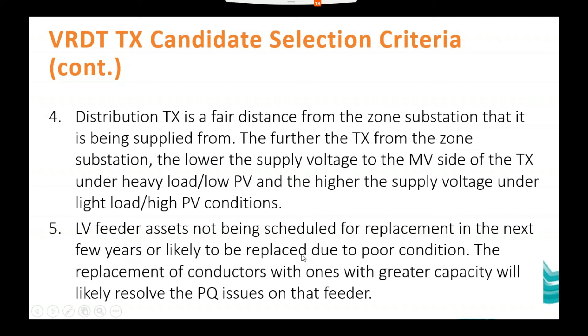And we also wanted to do it where the LV conductor assets were in relatively good condition. We didn't want the conductors to be in poor condition, because if those assets are in poor condition and you need to replace them, chances are you replace them with new conductor, which is a new standard, which is thicker conductor than the old days, and that inherently has lower impedance values. And usually when you fix it with those kinds of conductors of lower impedance, the voltage problem also goes away.